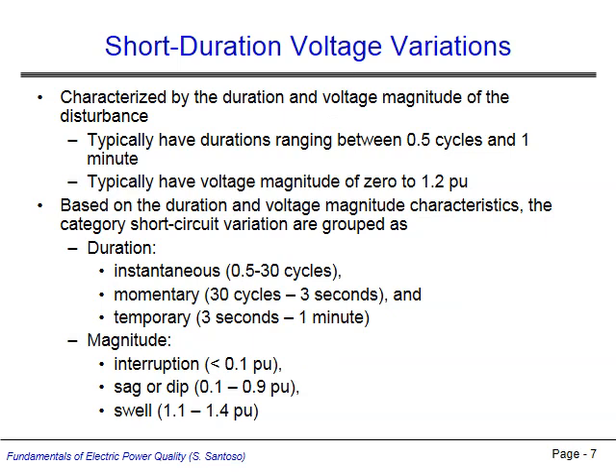Short duration voltage variations are a type of RMS variation. Short duration signifies that they typically last from as short as half a cycle to as long as one minute. The RMS voltage during this kind of event typically ranges from 0 to 1.2 per unit. These voltage variations can be further classified by their specific duration and magnitude. Variations lasting from 0.5 to 30 cycles are called instantaneous, those lasting from 30 cycles to 3 seconds are called momentary, and those lasting 3 seconds to a minute are called temporary.